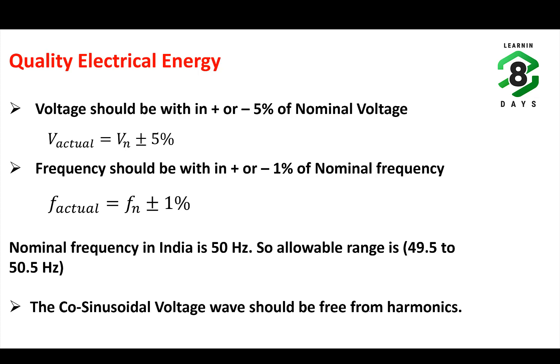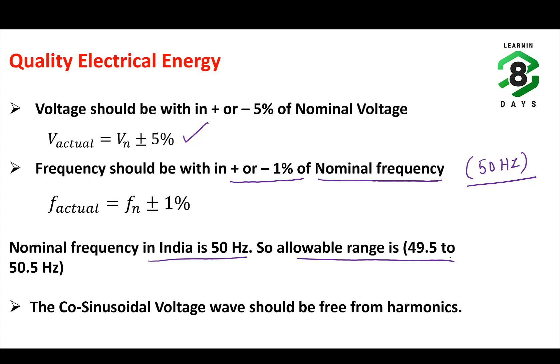What is quality electrical energy? Quality electrical energy should satisfy three parameters. First, the voltage should be within plus or minus five percent of the nominal voltage at any point in the power system. Second, the frequency should be within plus or minus one percent of the nominal frequency. In India, the nominal frequency is 50 Hz, so the allowable range for frequency is from 49.5 Hz to 50.5 Hz.